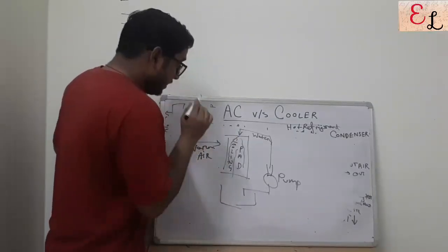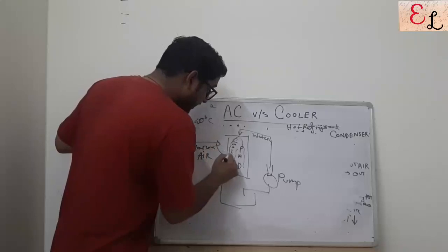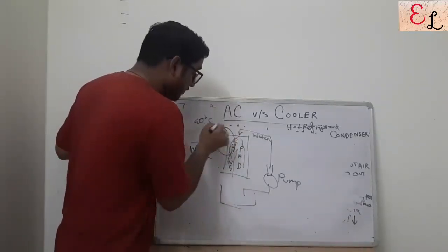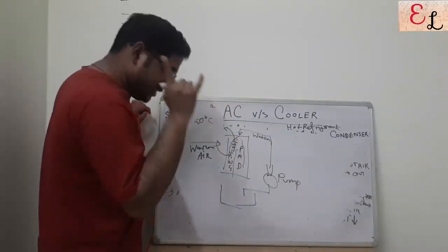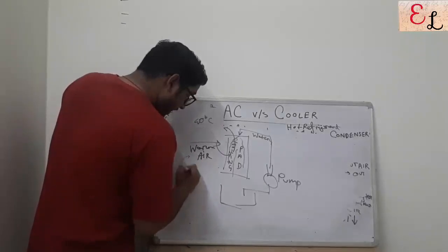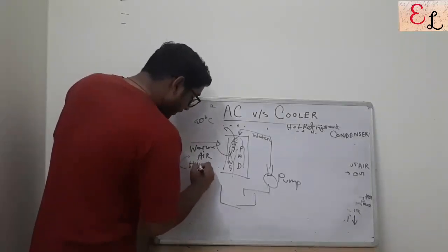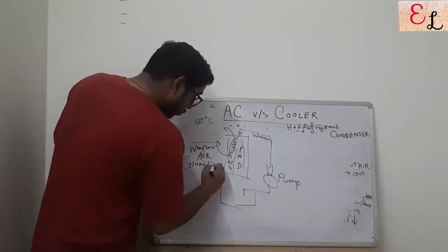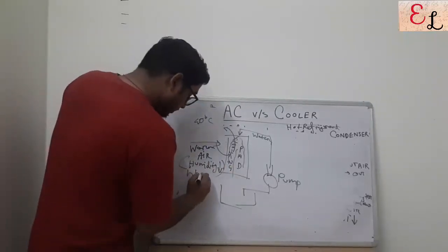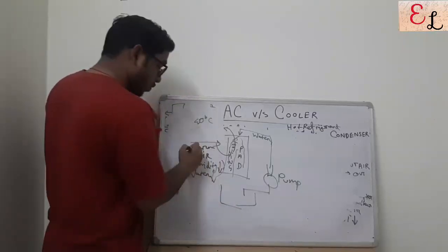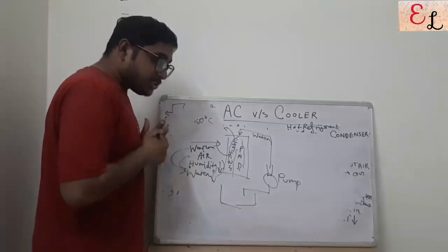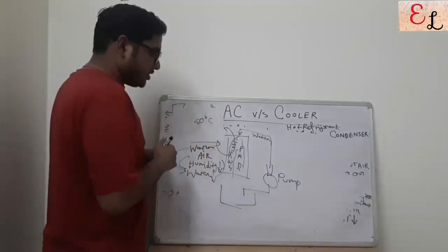What happens is, this warm air gives heat to the water so that some amount of water evaporates and goes into the system. This will only happen when the warm air has a low humidity. Humidity of the warm air is low, so water vapor is less in the warm air, and the pad is full of water. So a mass transfer of water will start occurring.